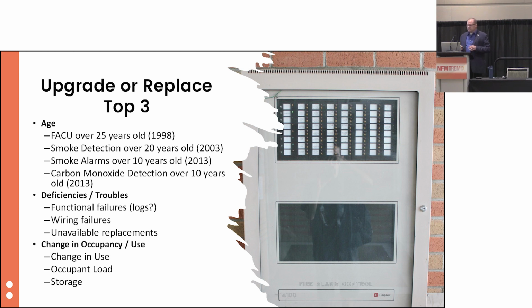As buildings change and adapt to new tenants and operations, the fire alarm system needs to change to meet those needs. For example, changing the use. So you have a business occupancy, but you need to fill it, and maybe your local college needs more classroom space, so you let them take over the 3rd floor for night classes. Well, that just changed that floor to an E occupancy, which requires a voice fire alarm system, period. So you may have to change your entire building's fire alarm system for that one tenant.